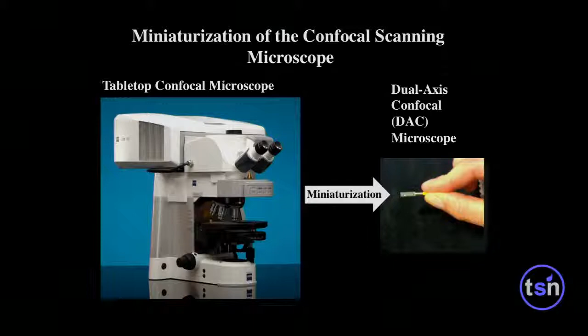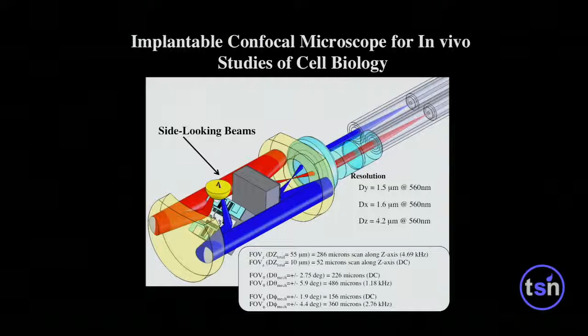So to do that, we had to change the architecture of a confocal microscope. Rather than illuminate on one path and collect on the same path, we have one illumination path and one collection path, represented here by the blue and the red, where the light comes down one path, hits a scan mirror that I'll show you in just a moment, and then hits a parabolic mirror acting as the lens, a second parabolic mirror, second scan mirror, into the tissue, and the fluorescence is then collected on a mirror image. We don't get quite the resolution that you'd get with a standard confocal. Standard confocal will get you down below a micron. Here we're around a couple of microns to 4 microns in the Z, depending on wavelength. And this design enables the use of very simple optics. This catadioptric lens is both transmissive and reflective and can be simplified, and also provides a very long working distance, so we can scan this beam with the 2 scan mirrors.